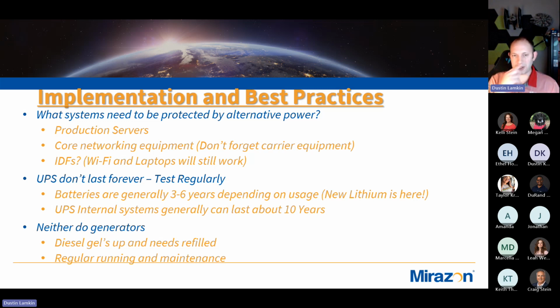We'll talk about that more in a minute. But for internal UPS systems, while batteries might last 3 to 6 years, we don't want to just keep replacing batteries over and over, because the internal components die too. Generally we say replace the batteries 2, maybe 3 times, but then you should replace the whole UPS itself, because the switching technology degrades. Brownouts really work on those surge and noise filters and cause all kinds of problems, they start humming, and you can hear it when they're going bad. So around 10 years is when you need to replace the unit, and that works out well with lithium batteries, swap the whole unit out.